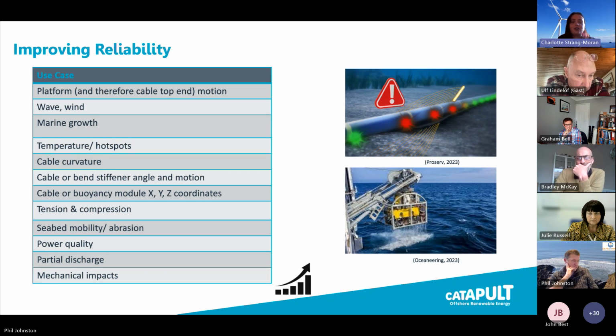If you're looking at your bend stiffener angle and motion, you could look to strain monitoring again, but more sort of external strain monitoring. Buoyancy module coordinates, you can either look at cable motion monitoring or cable angle monitoring as well. Tension and compression, there's hydrophones, depth gauges. Seabed mobility, you could be looking at acoustic sensing. Power quality, distributed electrical sensing. Partial discharge, you could be looking at, again, well-established online partial discharge and DTS. You could be looking at acoustic sensing. And mechanical impacts, where a number of these different technologies could support to understand various different local mechanical impacts.